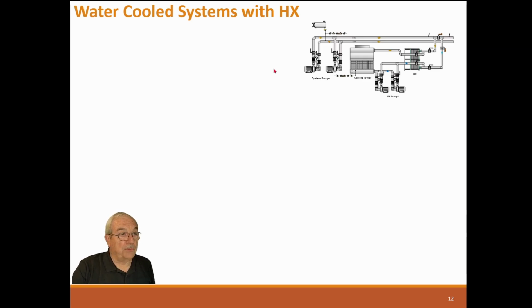So what we came up with as an alternative is we bought a flat plate heat exchanger, installed a second set of pumps, and use a standard cooling tower. And what we do is we run these pumps, and we run the cooling tower water through the heat exchanger.